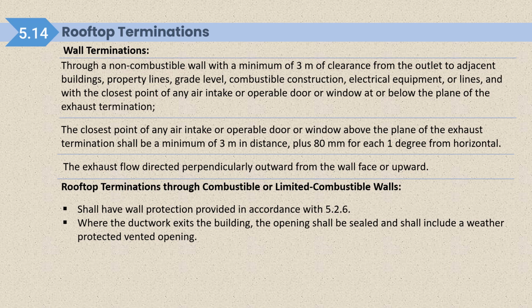Termination through combustible or limited combustible walls: we have already seen in 5.2.6 that where the ductwork exits the building, the opening shall be sealed and shall include a weather protected vented opening. So we have covered these requirements in the previous slide already.